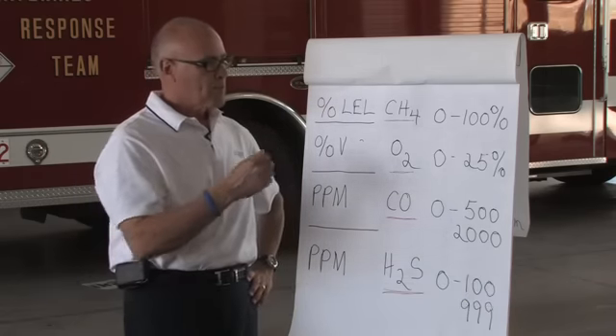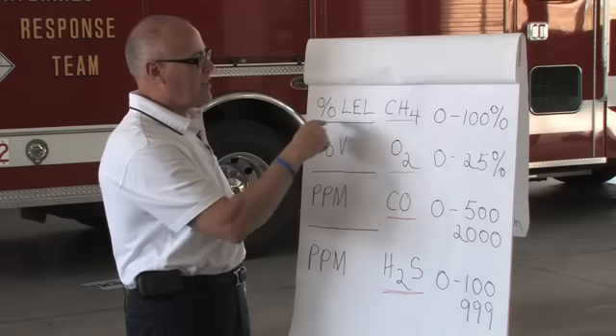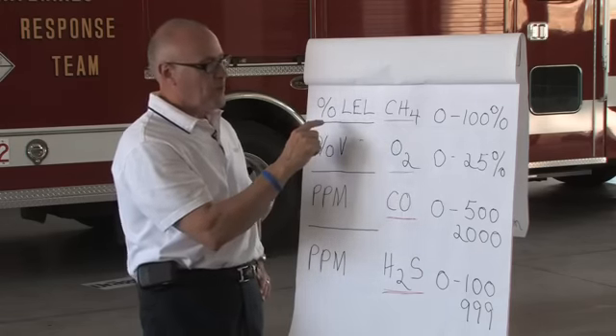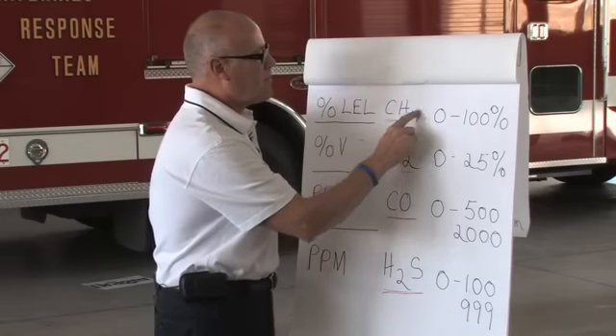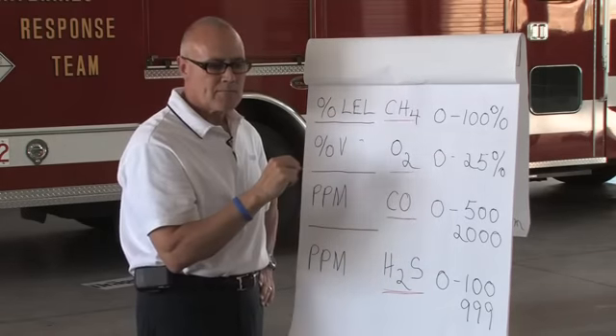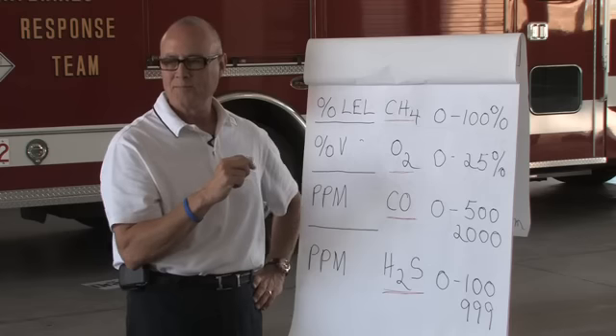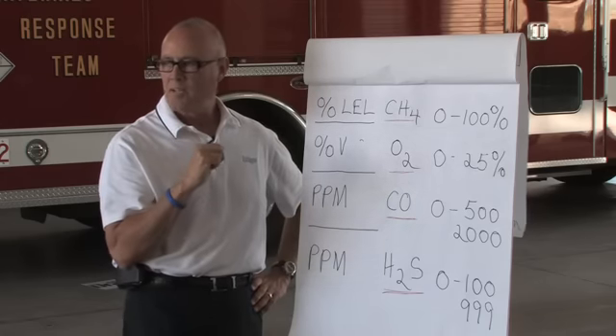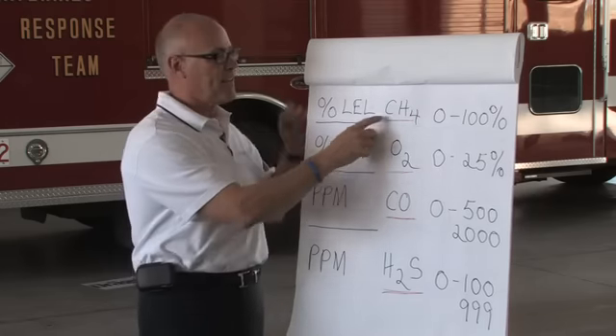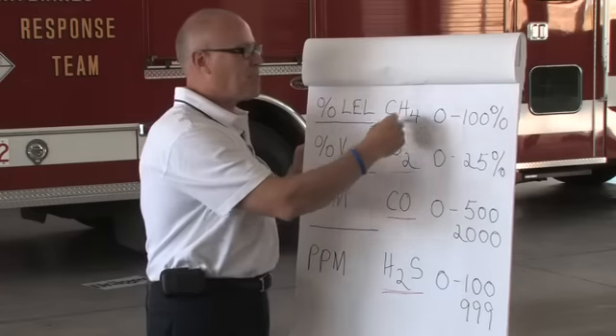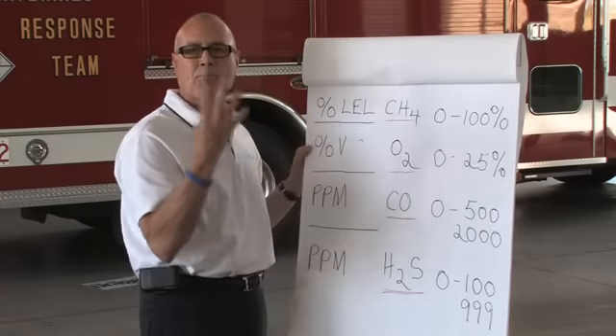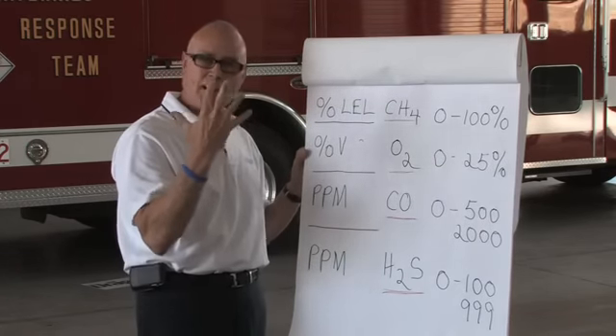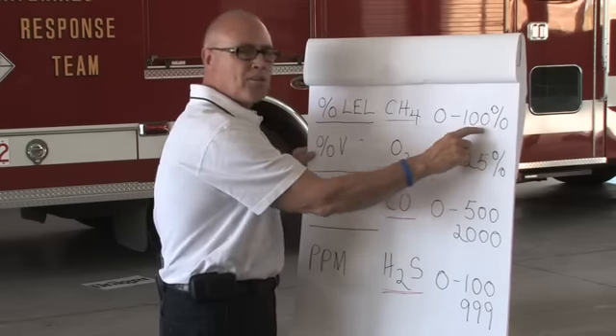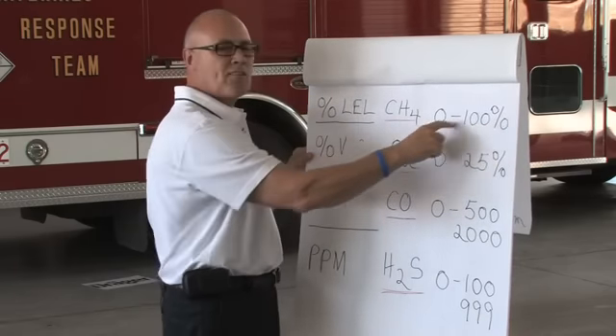So if you want to look at this in perfect math, 1% by volume of CH4 is 20% of the LEL. 2% by volume of natural gas is 40% of the LEL. 3% by volume is 60%. 4% by volume is 80%. 5%, you've hit your lower explosive level, and that is your explosion point.